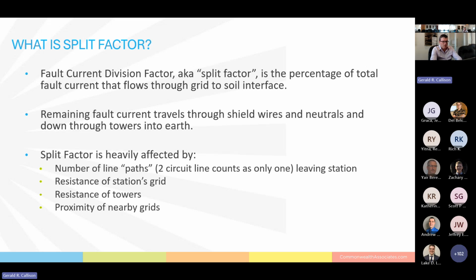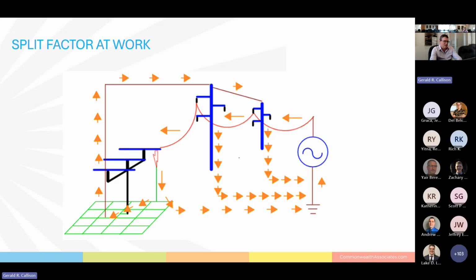And another factor is, are there any grids nearby? If there's a grid nearby, that's going to help the ground grid quite a bit, and that will lower your split factor. So let's look at a picture of split factor. Here we see an enhanced version of our previous picture where we showed a source providing ground current through a transmission network to a single line to ground fault in a station. And we see that some of the current is leaving the ground grid through that grid to soil interface, through the soil back to remote earth. Another portion of this current is traveling through the ground grid up through where the shield wire or distribution neutral is grounded, through the shield wire, back down each tower into the earth and back to remote earth.